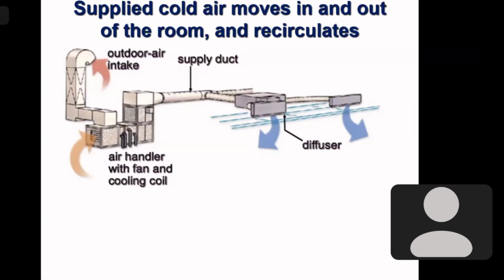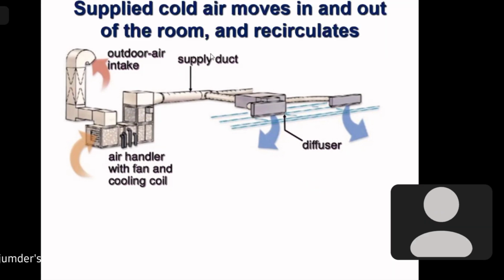So, we supply cold air in the room. You see, cold air is being supplied in the room by the diffuser. It picks up the latent heat from the room. It removes the latent heat from the room. And then we take the air back. With red arrows, you see, we are taking the air back to pass it over a cooling coil. The cooling coil is housed inside an air handling unit. We call it an air handler or air handling unit.